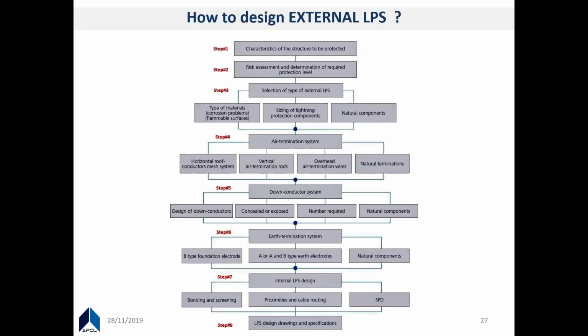So designing of external LPS, we have already started with the risk calculation, starting with the characteristics of the structure to be protected and the risk assessment. We just had a look; we did not go individually because that itself will consume like 5 or 6 hours. Definitely, if I'm going to go through each and every detail, it will take more than that. That's why you have to do the calculations and attempt calculations to see what needs to be conducted.